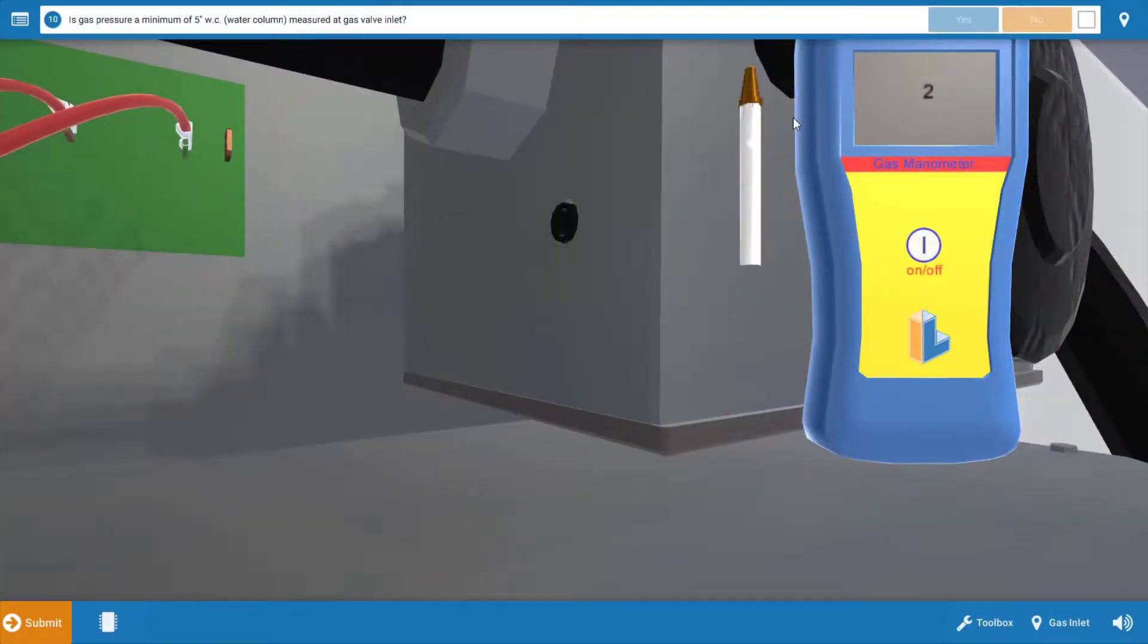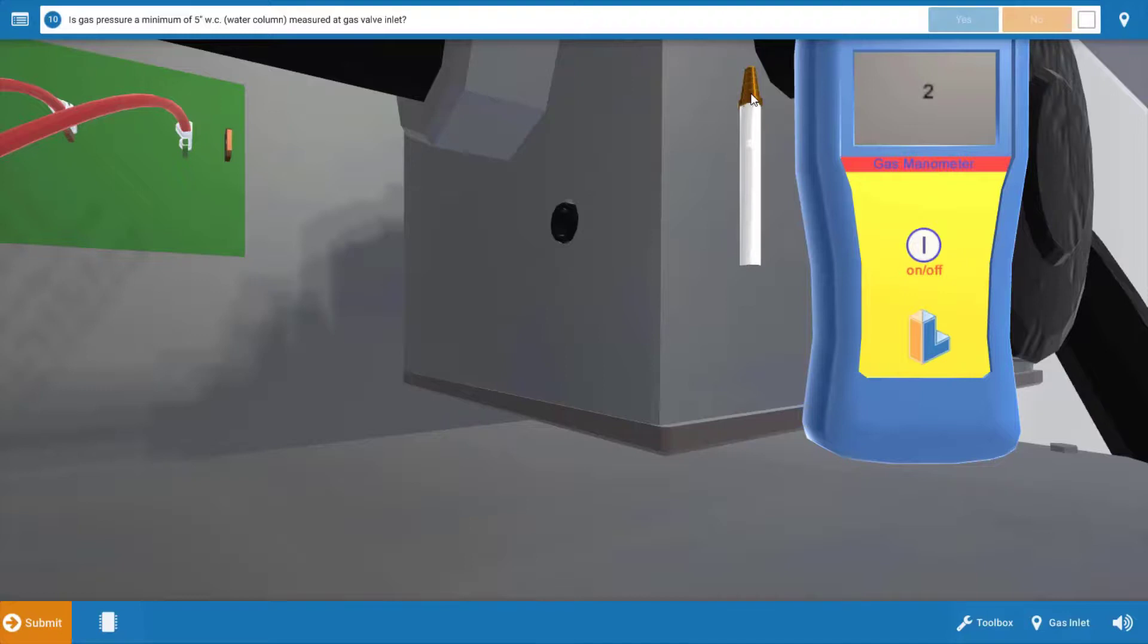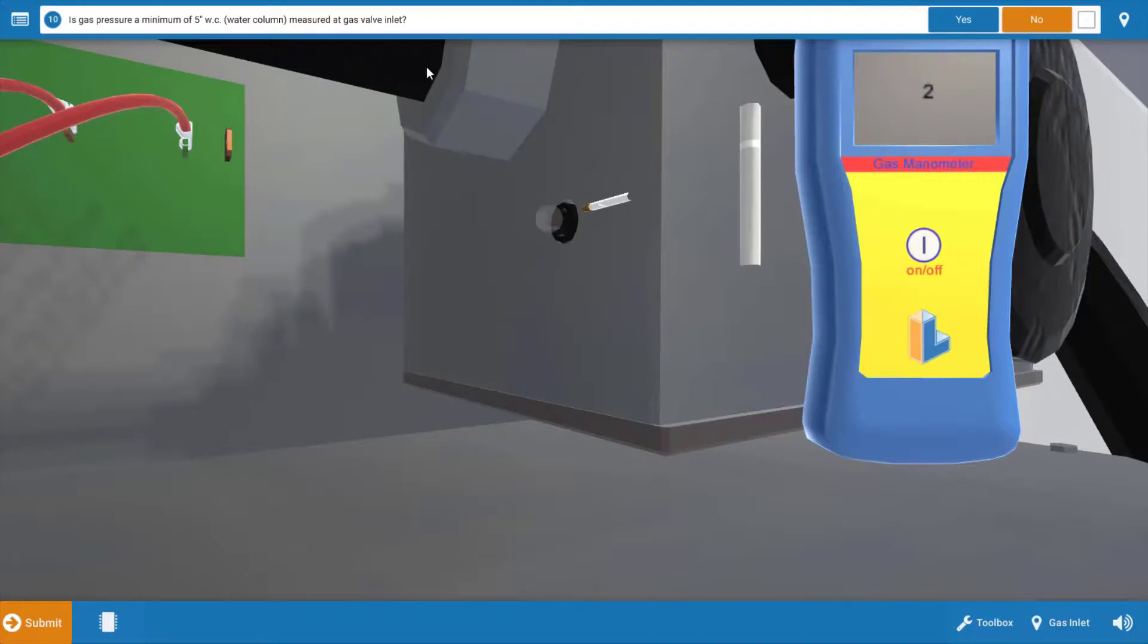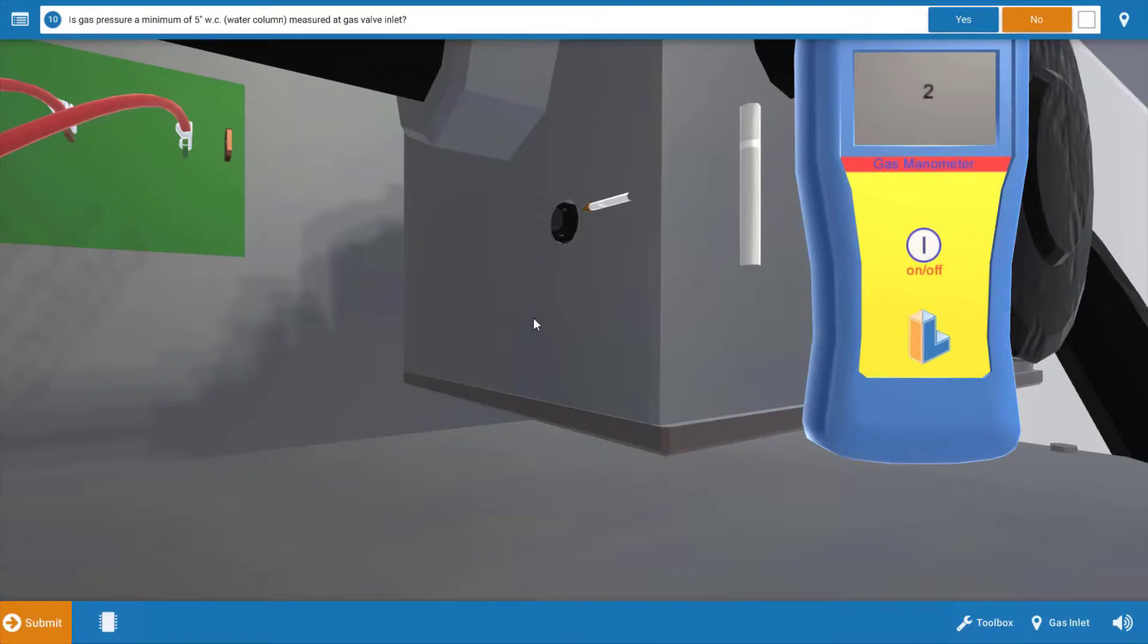Our next step is to check the gas pressure coming in from the main service or from the utility company. This should be a minimum of five inches of water column here. So we're going to drop the manometer probe and install it in the main side of the gas valve here. And we see we only have two inches of water column coming in here. So we have an issue here with the main gas service. We should have had a minimum of five here. You could evaluate the gas pipe sizing on a new installation, but overall, this generally means you're going to need to contact the utility company to see what's going on with the main gas pressure.